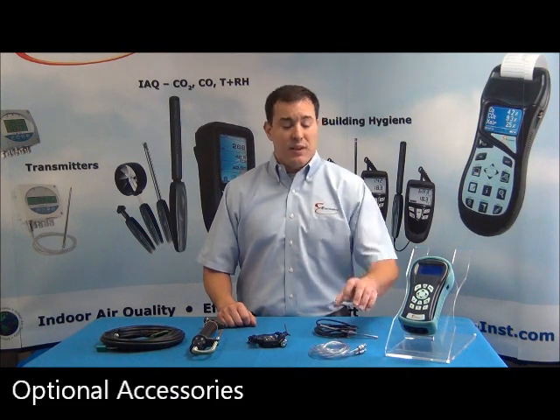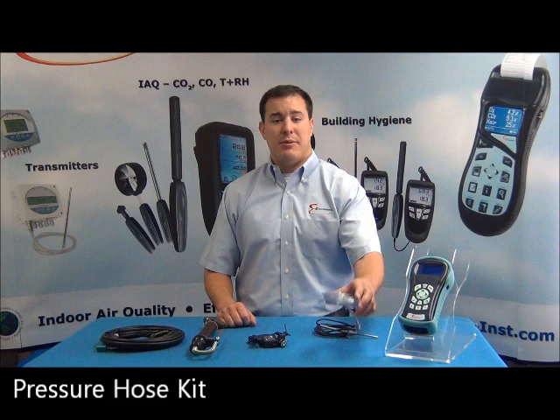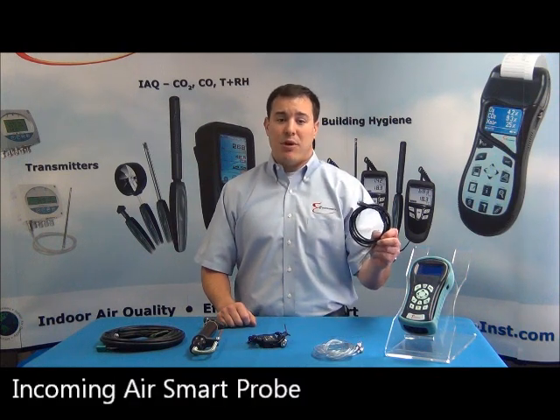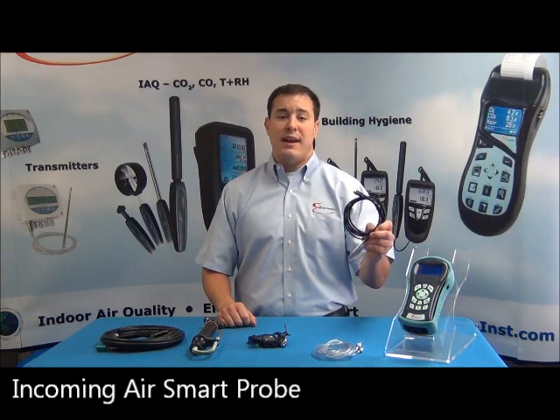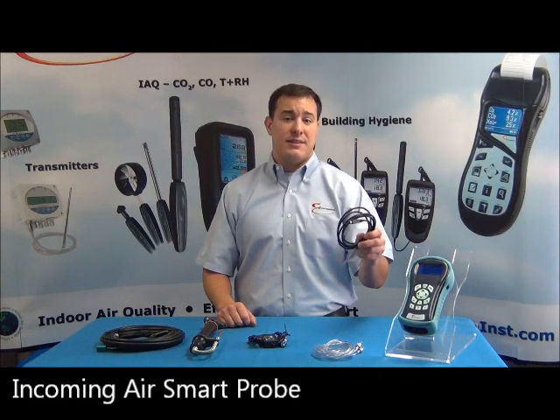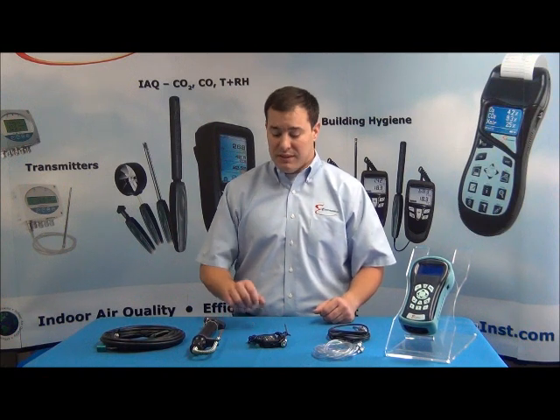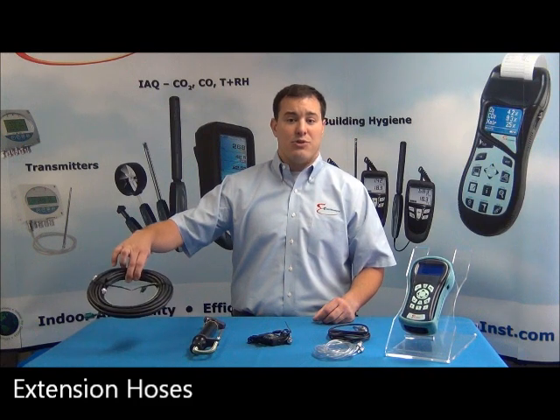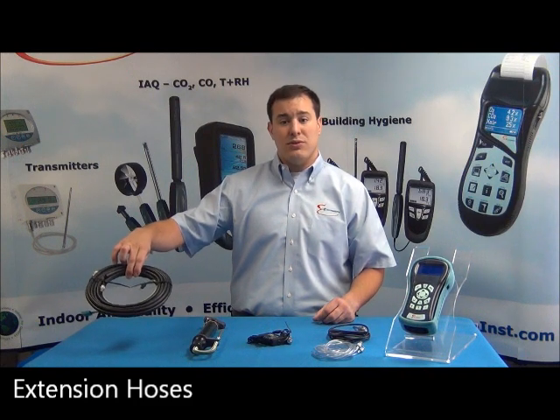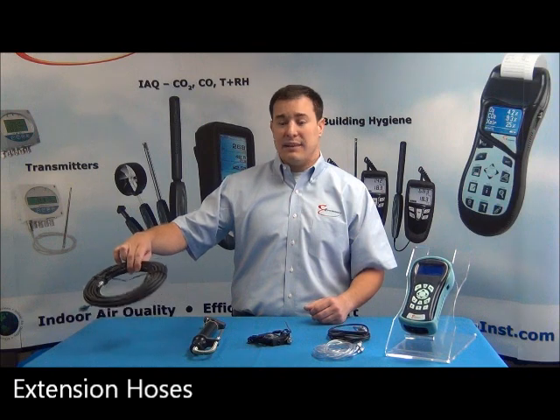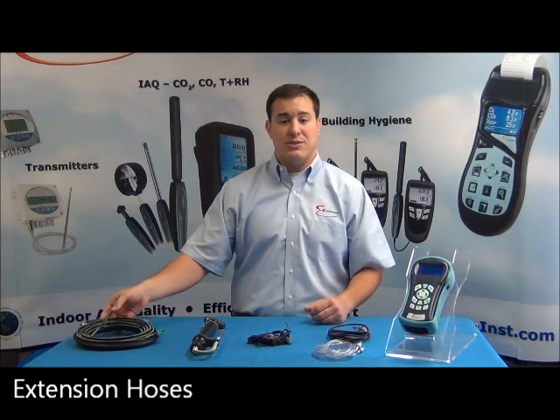Here are some of the optional accessories that are available for the BTU900. The pressure hose kit for your built-in differential manometer. The incoming air smart probe we discussed earlier that is necessary for any high efficiency forced air and condensing systems. This comes standard with all of our high efficiency kits. The DC charger for your car or truck. This allows you to warm up the unit or charge it before you get to your first job or in between jobs. The extension hoses for larger boilers that allow you to still be at the burner controls when the probe is far away in the stack. That is great for larger, more commercial applications.